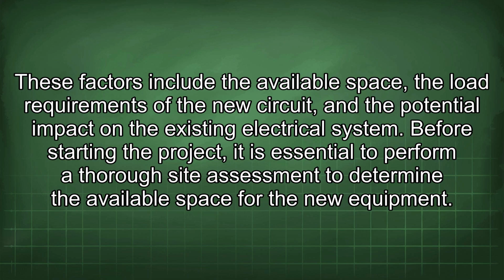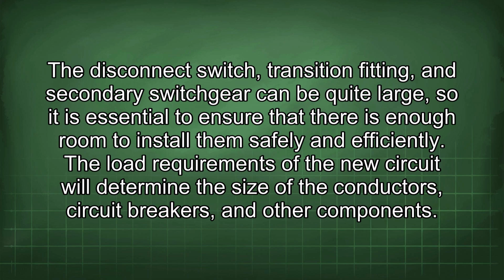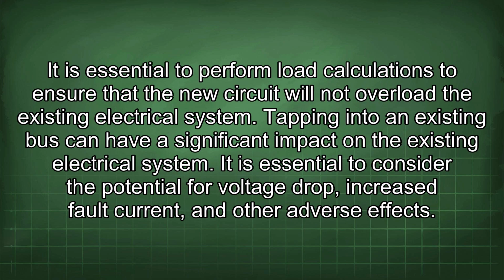electrical system. Before starting the project, it is essential to perform a thorough site assessment to determine the available space for the new equipment. The disconnect switch, transition fitting, and secondary switchgear can be quite large, so it is essential to ensure that there is enough room to install them safely and efficiently. The load requirements of the new circuit will determine the size of the conductors, circuit breakers, and other components. It is essential to perform load calculations to ensure that the new circuit will not overload the existing electrical system.